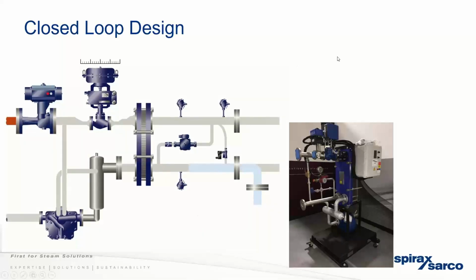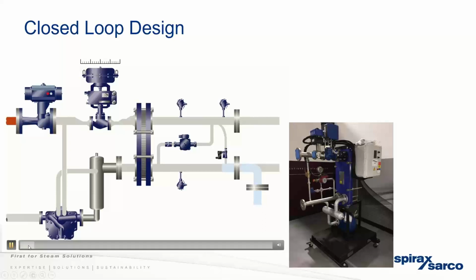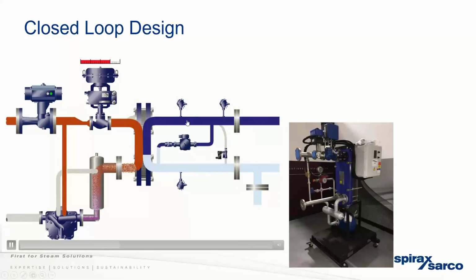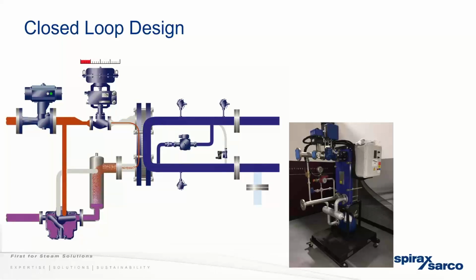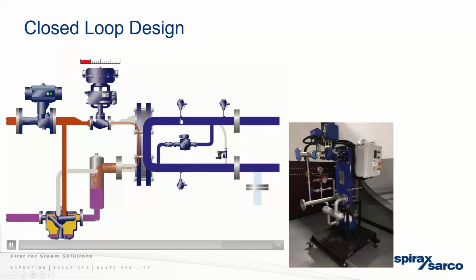And a bit of a video here. So you can see the cold water coming through. On the right-hand side, we have a bunch of temperature sensors. This is the steam side. So steam is going to start entering the heat exchanger, start heating this water. There's a recirc loop here to continually ensure our temperature control is at the point we want it to be for sanitation. So by continually having feedback, there's always flow across the temperature sensor. And this makes sure we have accurate temperature control leaving the heat exchanger.